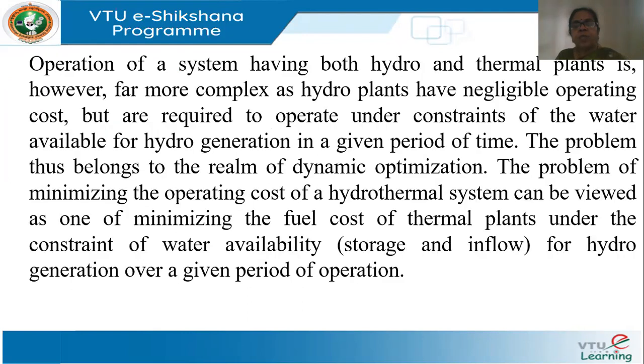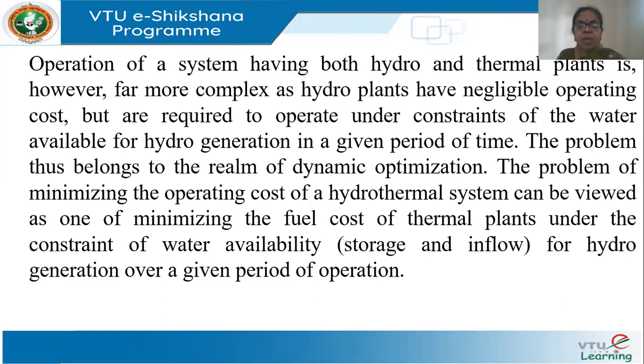Operation of a system having both hydro and thermal plants is far more complex, as hydro plants have negligible operating cost but are required to operate under constraints of the water available in a given period of time. This is a dynamic optimization problem. The problem of minimizing the operating cost of a hydrothermal system involves minimizing the fuel cost of the thermal plant under an additional constraint of water availability of the hydro plant. The objective function is still minimization of cost, with water availability as a constraint.